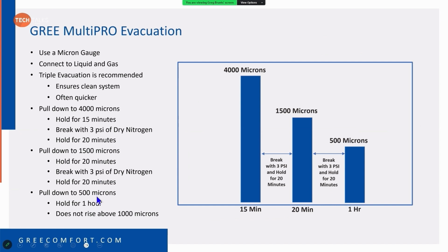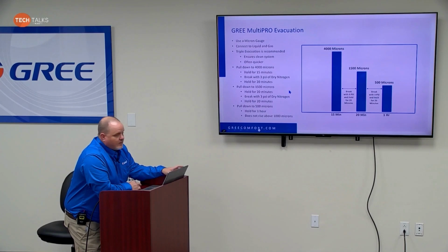I love when guys say they let the vacuum pump run all night. There's no reason for you to have to run a vacuum pump all night. You should be able to use a micron gauge, and if your microns don't keep dropping, then either you need to break with nitrogen so that you can get your vacuum to come down, or you may need to change the oil in your pump. Or, like we always talked about in many of our trainings, use core removal tools. Get that Schrader core in that service valve out of your way so that you get a better flow rate and you'll achieve these vacuums a whole lot faster.